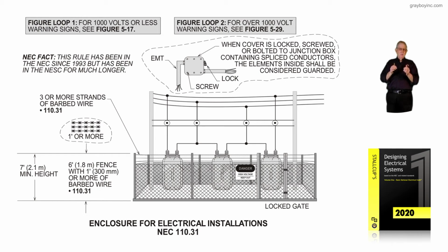They will place their switchgear in the substation, either in a weatherproof enclosure or in a design-built room for it with air conditioning, cooling, because they have sensitive electronic equipment mounted in that particular room with service equipment. And then it's feeders going up to each individual facility, which provides a lot of flexibility for the user.